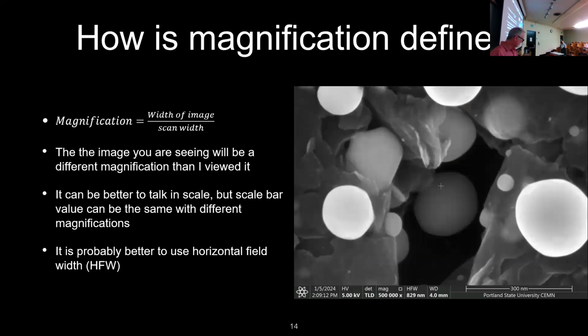So it's important to understand how magnification is defined. Some people in here might be old enough to have worked with film on microscopes. In the old days, film was usually Polaroid 545, which is 4x5 inch, so magnification was a standard thing. People understood what it meant. In the days of digital microscopy, we define magnification as the width of the image over the width of the scan. So if you're seeing this on the big screen in the room, it's definitely much higher magnification than on the monitor on my microscope. Maybe some people online are seeing this on a cell phone or an iPad. That would probably be much less magnification than I had when I actually saw this.